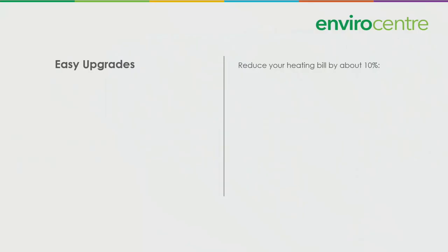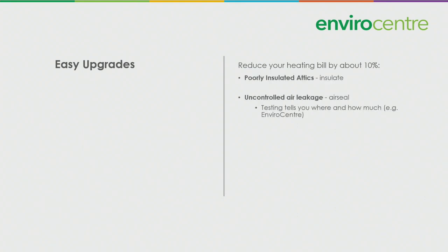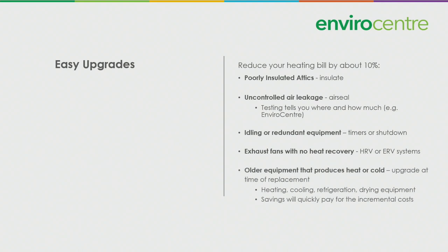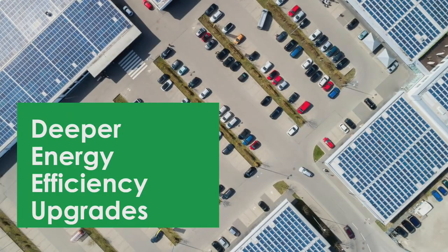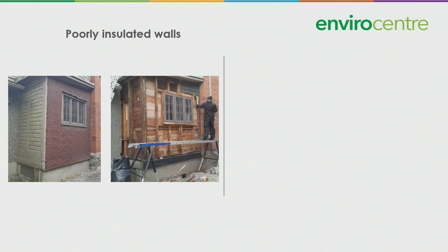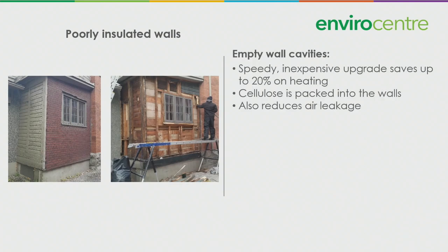The easy energy efficiency upgrades would include things that would reduce your heating bill by about 10%, such as poorly insulated attics, uncontrolled air leakage, idling or redundant equipment, exhaust fans with no heat recovery, older equipment that produces heat or cold. Deeper energy efficiency upgrades. This includes poorly insulated walls. If there are empty wall cavities, typically they're not opened up like the one in the picture here, they can drill small holes and implement a speedy, inexpensive upgrade that can save up to 20% on your heating bill. The cellulose is packed into the walls, and it also reduces your air leakage, so you get a lot of bang for your buck.